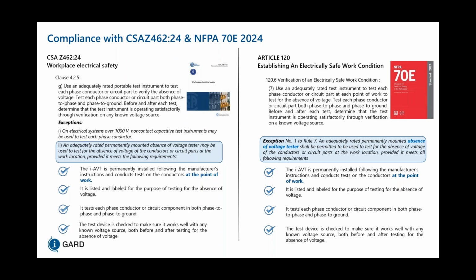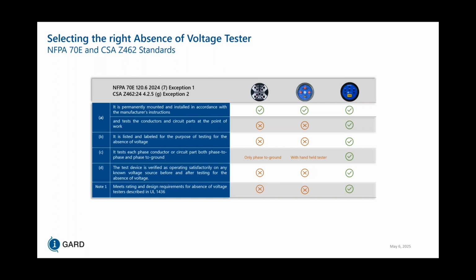It tests each phase conductor or circuit component in both phase to phase and phase to ground, and the device is checked to make sure it works well with any known voltage source, both before and after testing for absence of voltage. The same exception can be found in section 120.6, rule number 7, and the same stipulations are dictated as well, which are closely mirrored on the Z462 side. So you can see here that the absence of voltage tester is able to tick off all of the boxes in relation to what an absence of voltage tester should do, in comparison to a voltage indicator and voltage test ports. In this case, the absence of voltage tester is the only right solution to confirm absence of voltage in a system, aside from the traditional method of utilizing a multimeter.